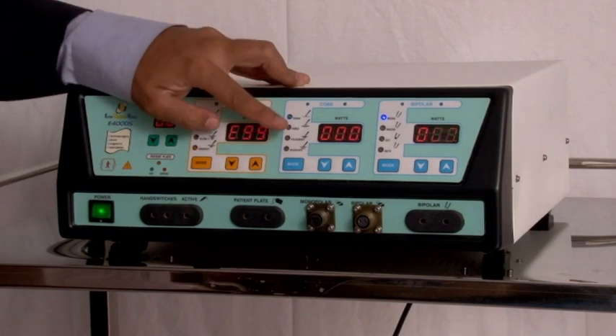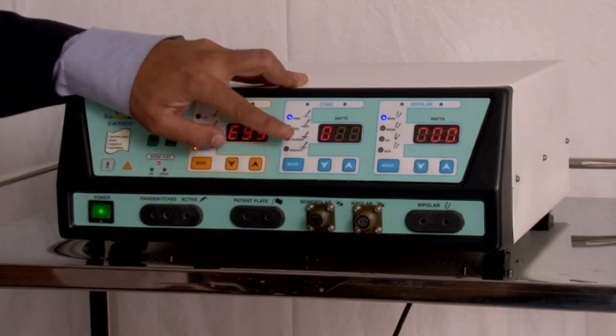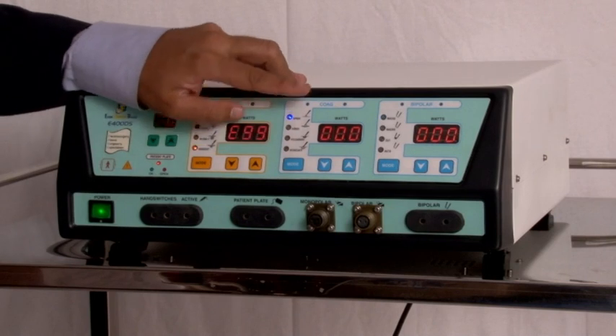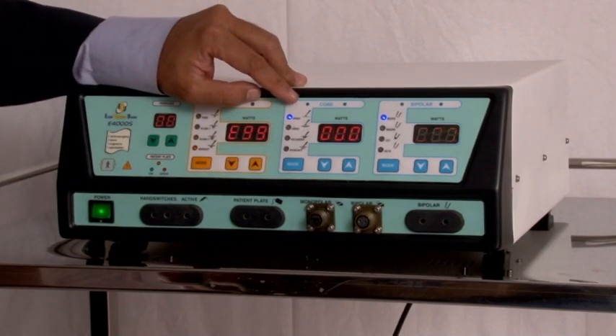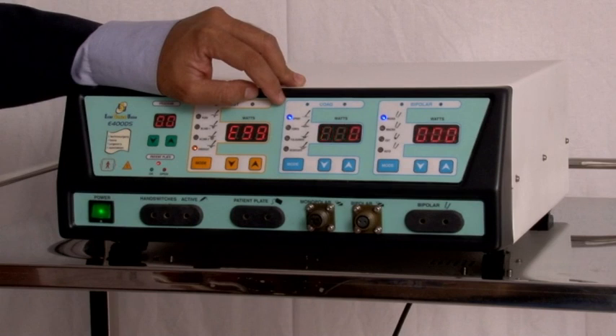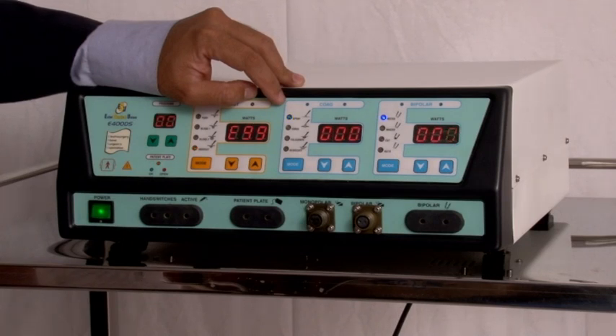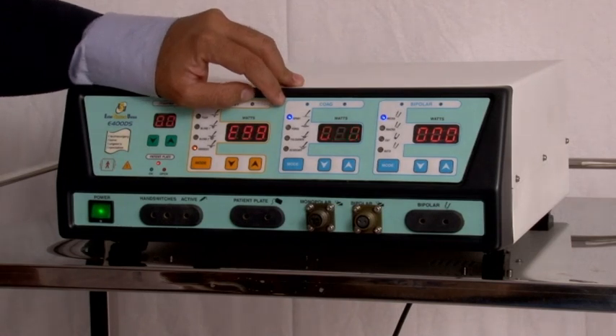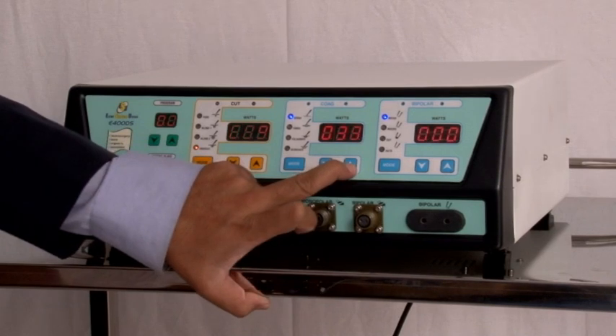Spray coag, a modulated pulse waveform with highest peak voltage, enables the surgeon to cover a larger area of coagulation by sparking from a longer distance without touching the tissues. This helps in speedy coagulation with less tissue necrosis and carbonization. Spray coag is always preferred by cancer and trauma surgeons. Spray coag has a maximum output of 120 watts.